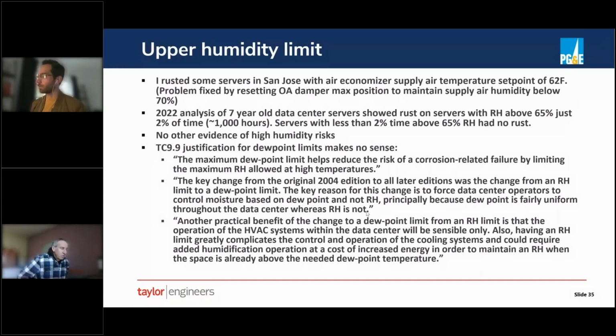Again, this doesn't make any sense to me. If you're concerned about RH, control RH. Yes, it's not uniform, but it's easy to control it everywhere to whatever RH limit you want to set. And that's how we operate almost all the data centers we work with. We just have an RH maximum set point, and the system controls to that. And then lastly, from the guideline, it says another practical benefit of the change to a dew point from RH is that the operation within the envelope will be sensible only, which doesn't make sense. It'll be sensible only whether it's RH or not. Also, having an RH limit greatly complicates control and operation and could require added humidification. Yeah, so I totally take issue with this.